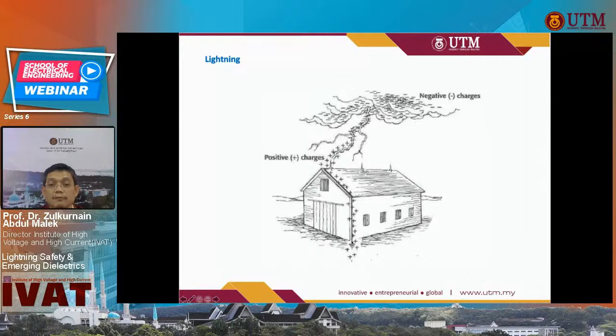And also the high current flow can cause induced voltage or spikes inside nearby loops. And if the house, for example here, is made of flammable material, the strike on the house itself can cause fire, for example, and therefore property damage. So we intentionally put air terminals at the top with a down conductor and a grounding electrode, so that the current can be safely discharged into the ground. So a good LPS will have all the components: good air terminals, down conductor, as well as a grounding electrode.